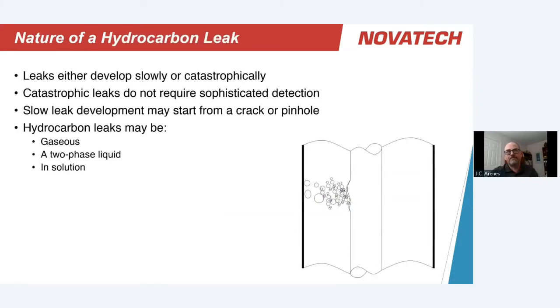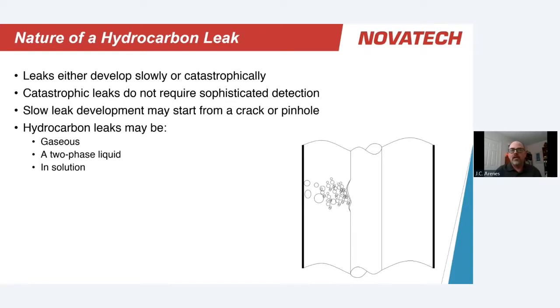The way leaks develop over time varies. They can be slow or very rapid. Obviously a rapid catastrophic leak doesn't need a sophisticated system to detect — it'll be very obvious. But slow leaks can develop very slowly, starting as just a crack or pinhole due to corrosion or stress cracking. The hydrocarbon can transfer into the cooling water in different forms: as a gas, as a liquid that does not readily dissolve forming an emulsion, fully dissolved in solution, or a combination of all three.